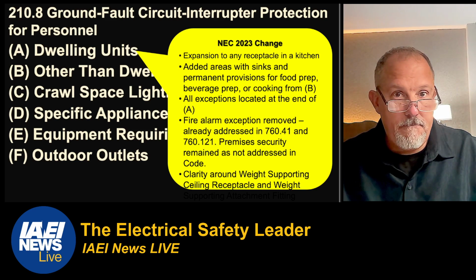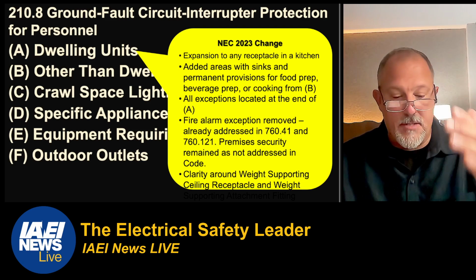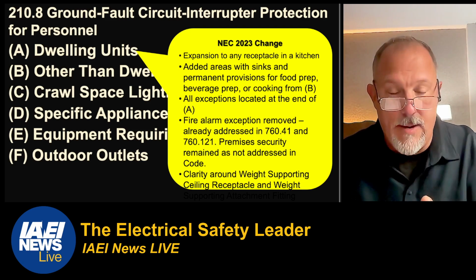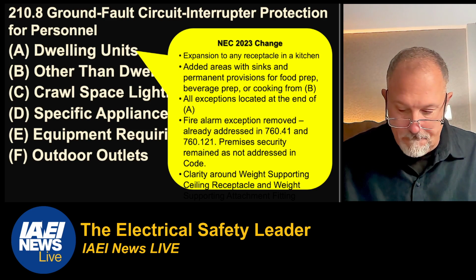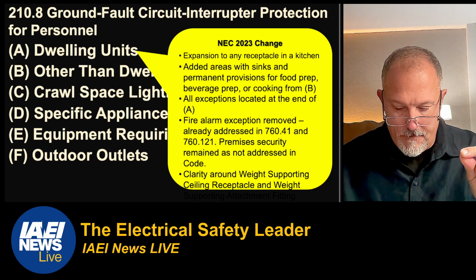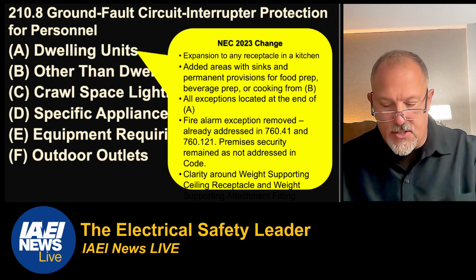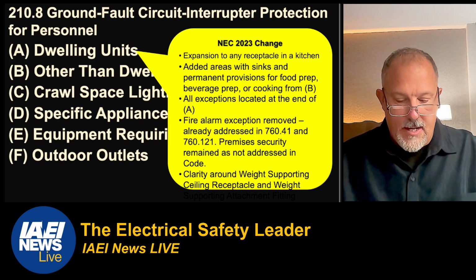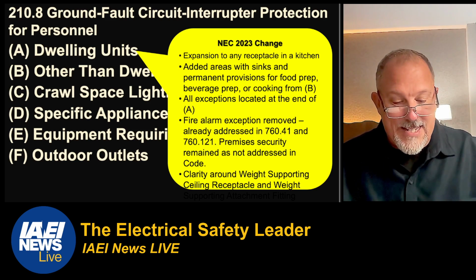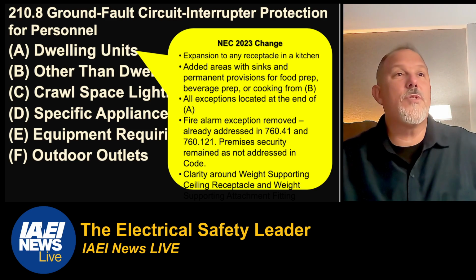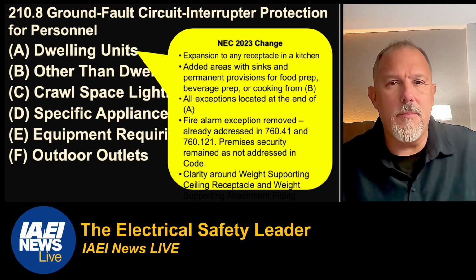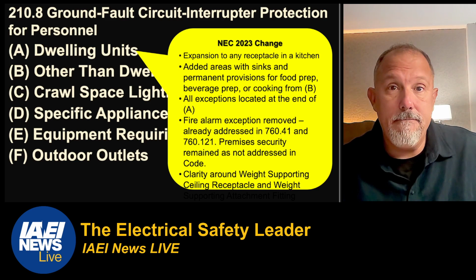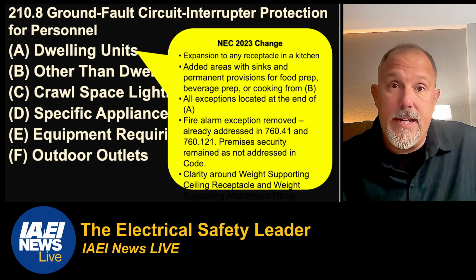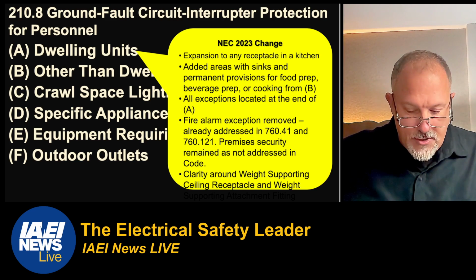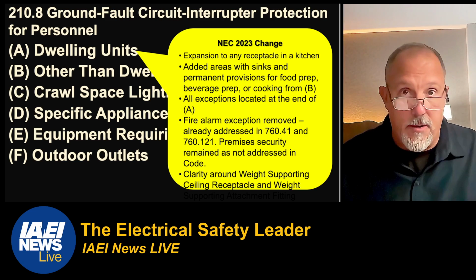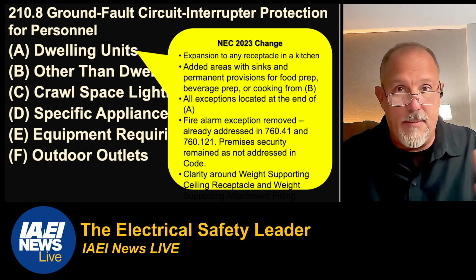All right, so all exceptions were located. Now, this is not a big change, but just be mindful that all of the exceptions are now placed at the end. And here's what we recognized. For example, remember we had an exception for receptacles supplying only a permanently installed, what we used to have, fire alarm or burglar alarm system are not required. And it was for the exception to basements. So somebody on the panel asked the question, what if the burglar alarm is in the garage? What if the burglar alarm is in my laundry? I need the GFCI protected. But then if you go back to the article that addressed, say, fire alarms, there was already the requirement that you can't put those on a GFCI.